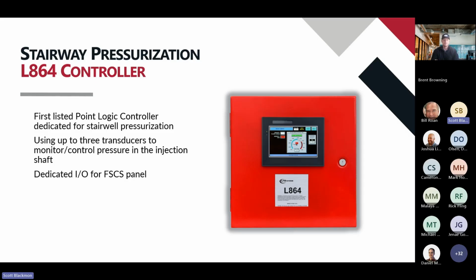So you can go into this panel, you can set it, run your test, feed that information to your BMS and have that logic and have those reports without having to activate the fire system, and call the fire department, things of that nature.